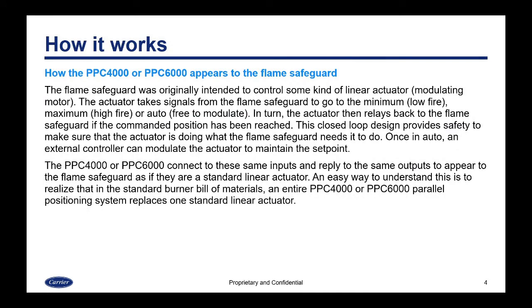So how does it work? How does the PPC4000 or PPC6000 appear to the flame safeguard? Well, the flame safeguard was originally intended to control some kind of linear actuator or modulating motor. The actuator will take signals from the flame safeguard to go to the minimum or low fire position, the maximum or high fire position, or to be in auto, which is free to modulate. In turn, the actuator then relays back to the flame safeguard if the commanded position has been reached. That would be, for example, when you're purging to prove that you're open, or when you go to the ignition position to prove that you're closed.